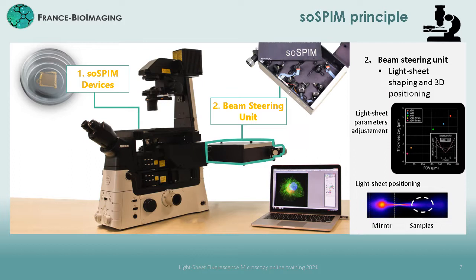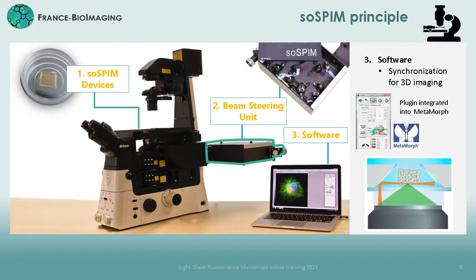The second component is a beam steering unit, which is directly plugged at the back port of the microscope and allows us to control the laser beam in the image plane. It allows us to adjust the light sheet thickness between 1 and 5 micrometers, for a length ranging between 10 to 300 micrometers, and to control the light sheet 3D position according to the sample location relative to our 45-degree mirror.